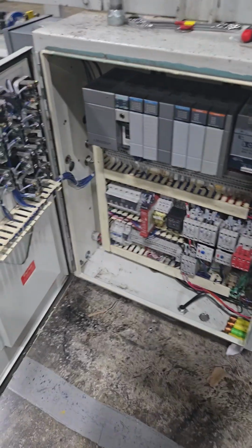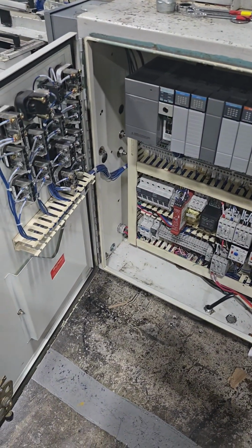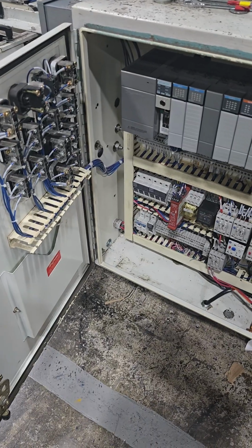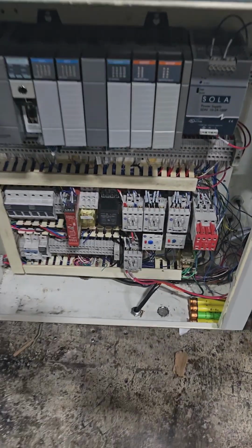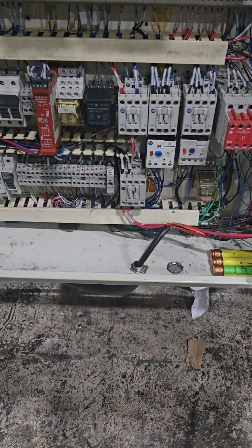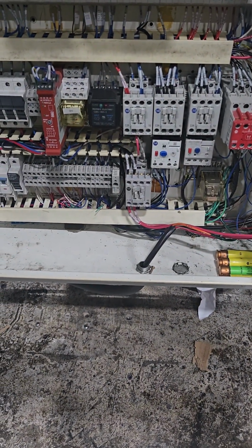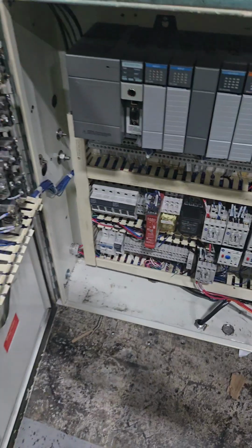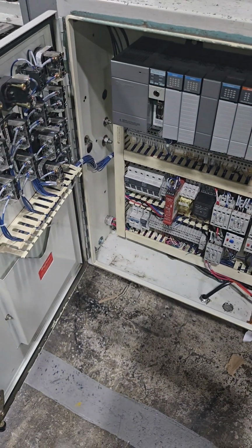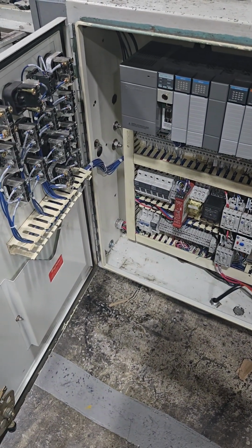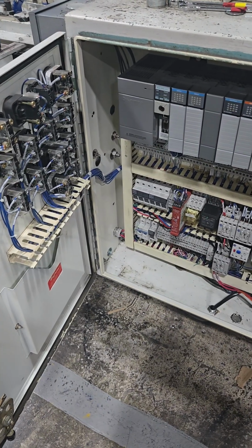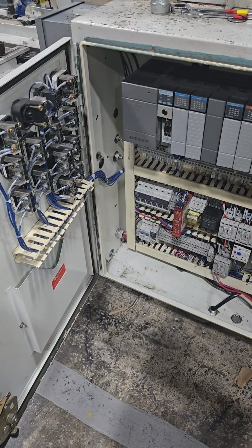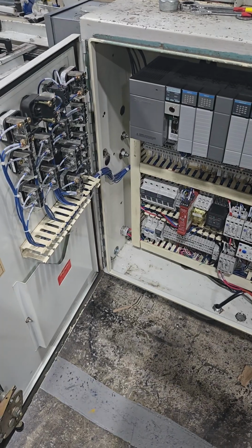As you can see in this cabinet, it has a PLC that controls the interlocks and has a program. And as you can also see, it gets rid of the majority of the relays. So how does relay logic work in practical systems? These relays respond to small electrical signals for opening and closing contacts that can control the larger loads. Although one is hardwired and one has a PLC, both are still wired and programmed to do the same job.